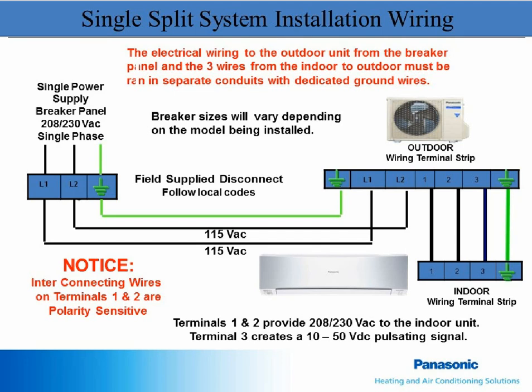Depending on the model, from the outdoor unit run 14-3 or 16-3 wire with a ground to the indoor unit. It should be stranded wire and the ground should be wrapped also. We do not require a disconnect at the indoor unit, but if the local code requires it, terminals 1 and 2 are the power supply. Terminal 3 is the controls communication wire.